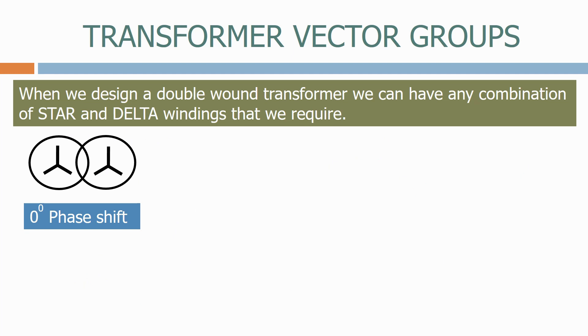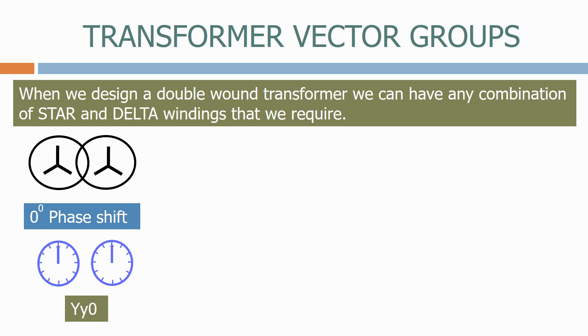If we want to represent the transformer as a symbol, we call it a Yy0, where the capital Y represents a star primary winding, the lowercase y represents a star secondary winding, and the zero represents a zero-degrees phase shift.